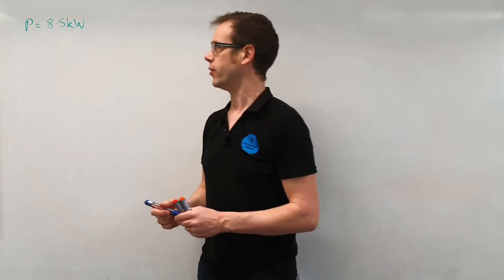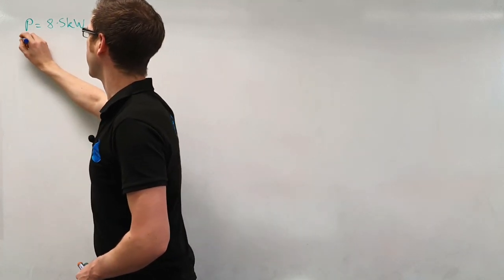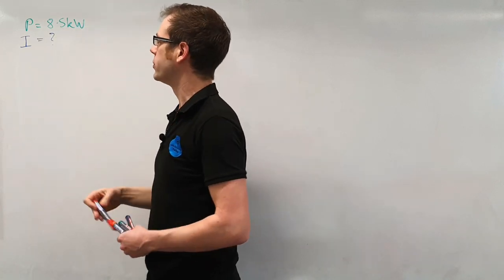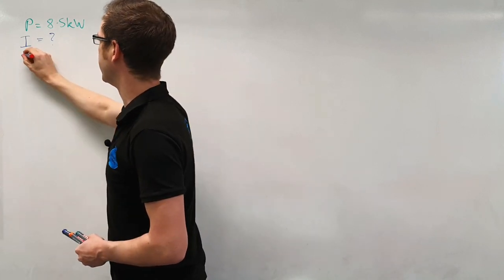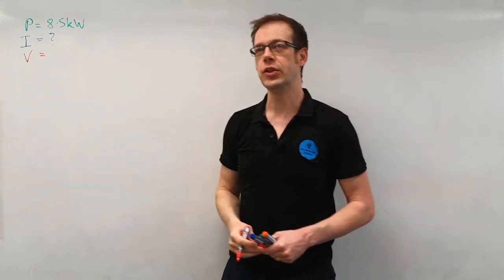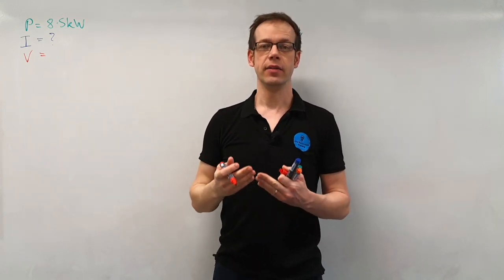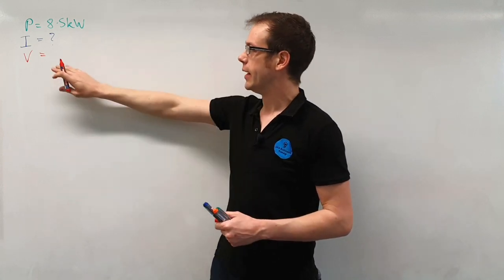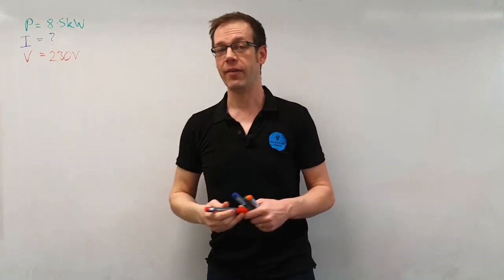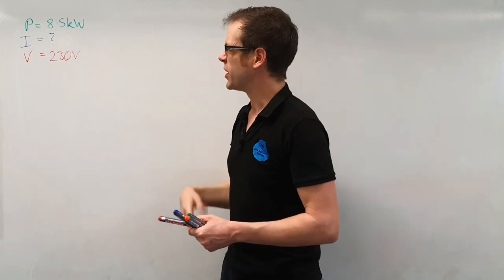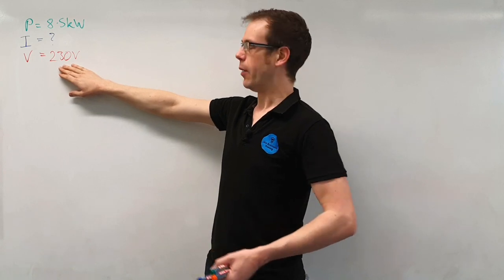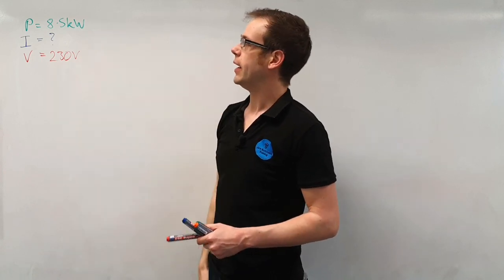Now we're trying to find the current in this video so we want to know what is the current going to be drawn by this shower, so I equals something we don't know yet. And we're also interested in, in order to calculate that current, we'll need to know what the voltage is. Now in the case of the voltage we know that the nominal voltage in the UK is 230 volts. We know that we can find that varying, it can go up or down from that value, but generally speaking when you do design work we use the nominal voltage which is 230 volts.